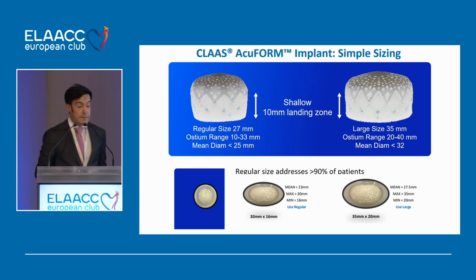From this point, we derive another point, that the sizing is very simple, because we have only two sizes of this device, and one size, the regular size, that is 27 millimeters, covers about 90% of left atrial appendage anatomies, because it covers an ostium range that goes from 10 to 33 millimeters, and we need just to have a mean diameter that is less than or equal to 25 millimeters. And given the foam conformability, we can cover very elliptic anatomies for the left atrial appendage ostium and landing zone.